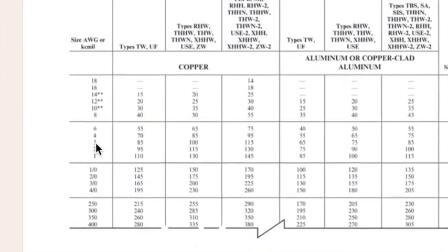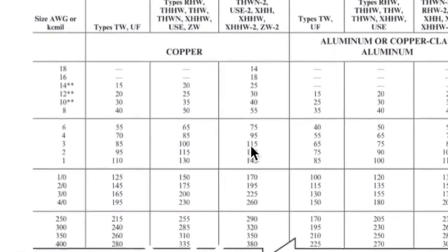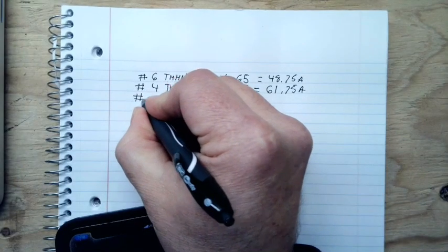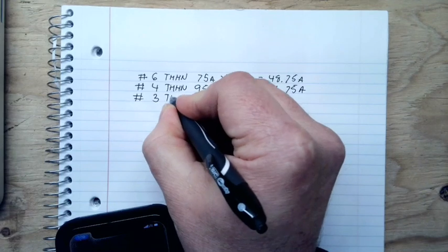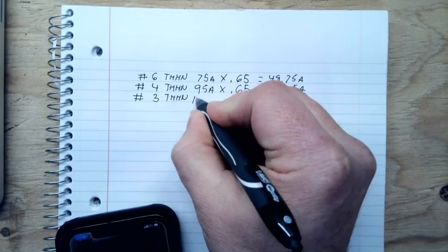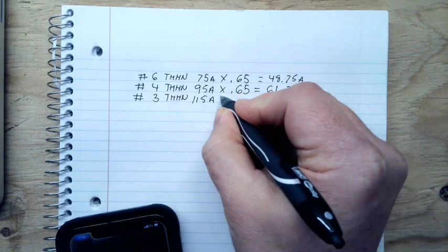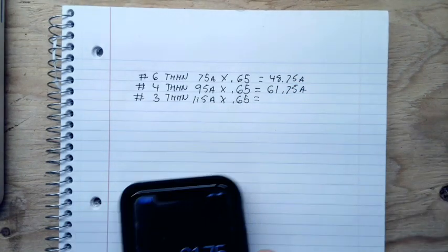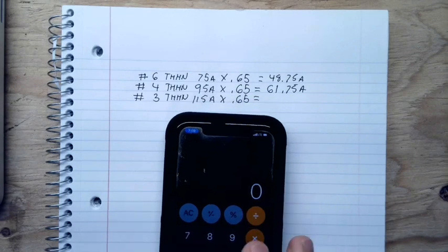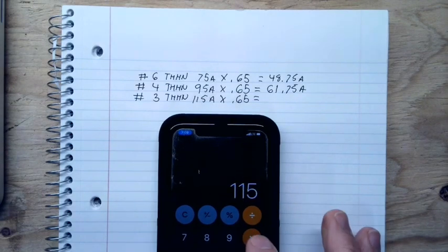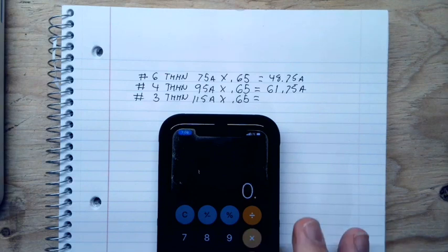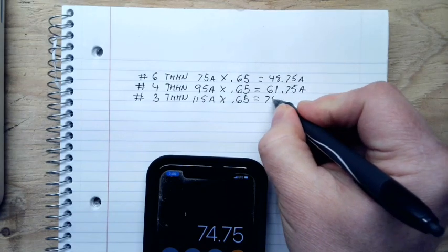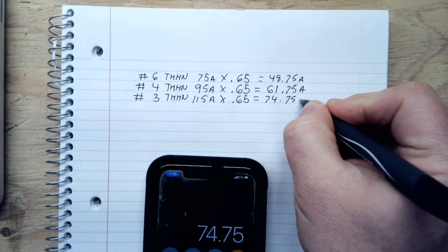Now I'm going to go to a number 3, which is good to 115 amps. So I'll write number 3, THHN, is good to 115 amps times the same correction factor of 0.65. And I'm going to go 115 times 0.65 is equal to 74.75, 74.75 amps.